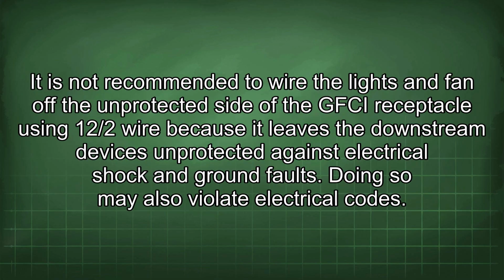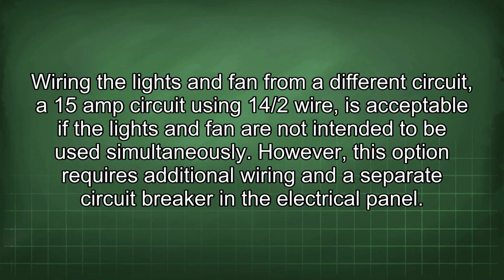It is not recommended to wire the lights and fan off the unprotected side of the GFCI receptacle using 12/2 wire because it leaves the downstream devices unprotected against electrical shock and ground faults. Doing so may also violate electrical codes. Wiring the lights and fan from a different circuit, a 15 amp circuit using 14/2 wire, is acceptable if the lights and fan are not intended to be used simultaneously. However, this option requires additional wiring and a separate circuit breaker in the electrical panel.